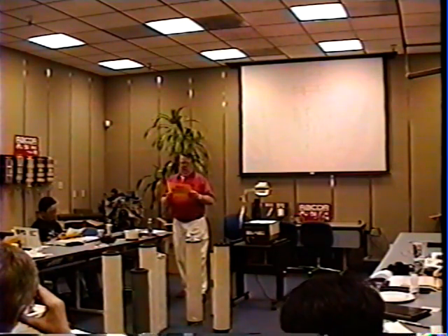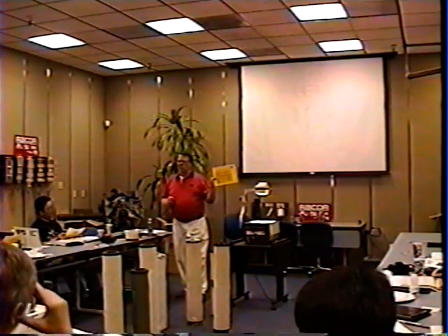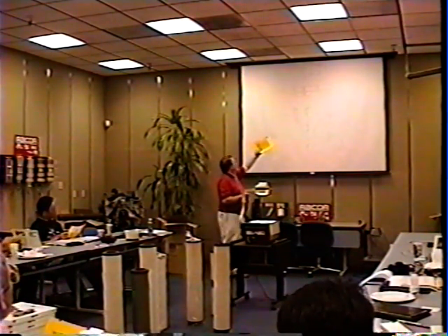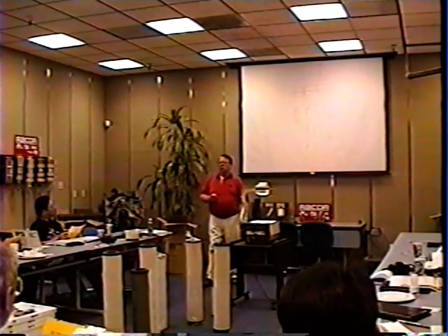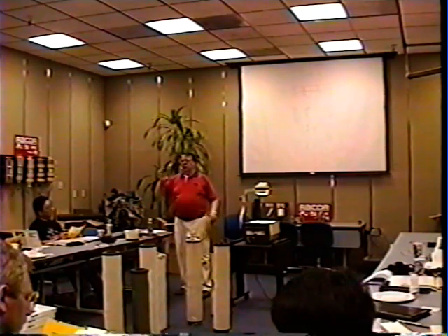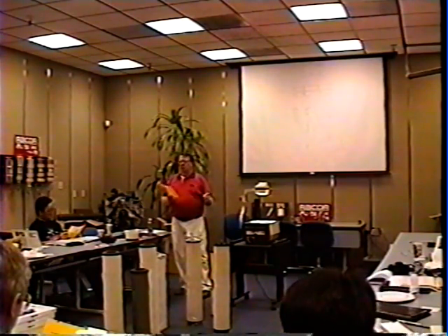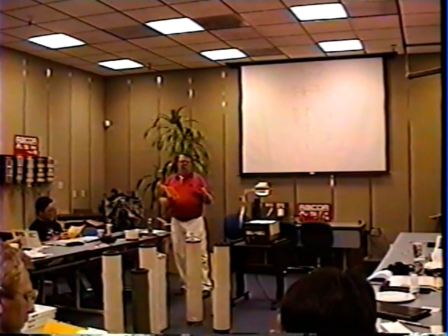So if you're outfitting it and giving the customer the target pricing, this is all U.S. list and USWD, and we shortly will have a transfer price card for Parker overseas boats. Okay, so here's all the different options. The most popular options are your differential pressure gauge. In this case, it's a piston type, but in our case, what we've seen most often is what you see out here in the hall, which is an actual gauge. And those work really well because they measure the true differential across your element. So you know how clean or how dirty your element is.